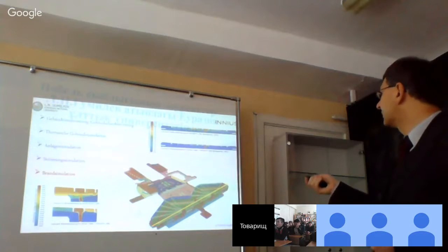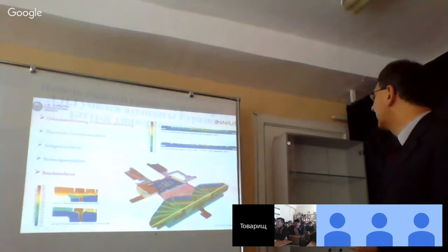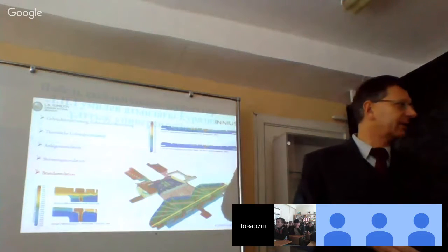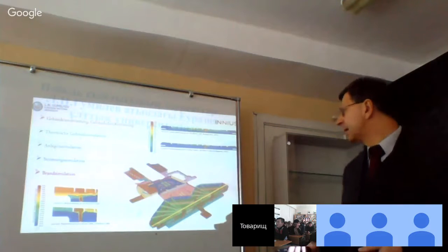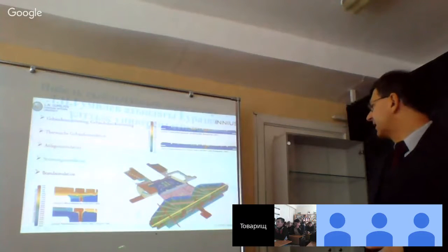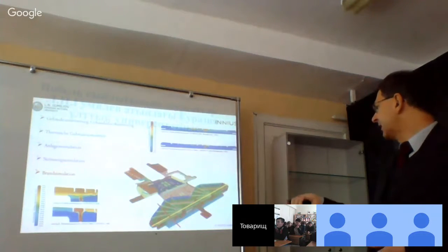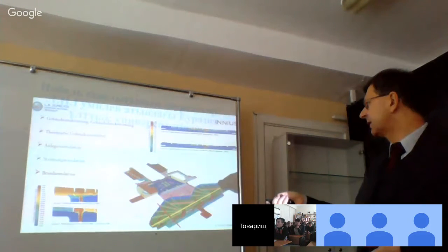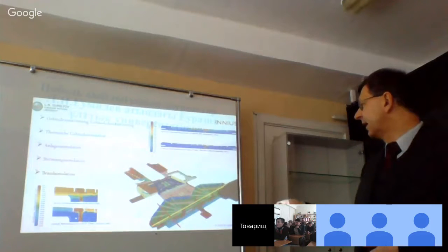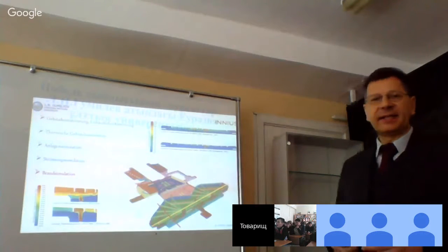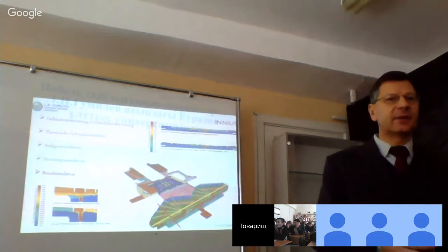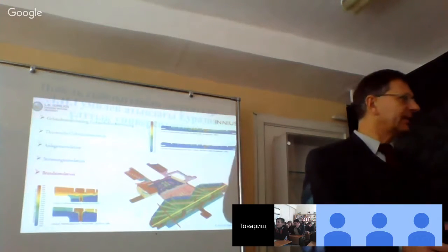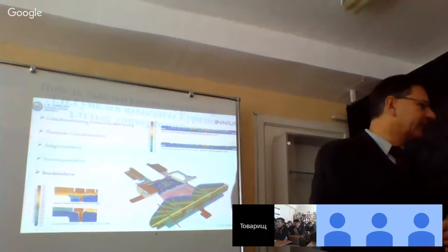If you compare these two cases, you see that you get a quite better result with half of the air quantity. We have the same result if we look at such a plane on this side, and you see 400,000 in the upper plane and 200,000 in the lower. It depends on the efficiency of the airflow within the room. That's why we use such methods.